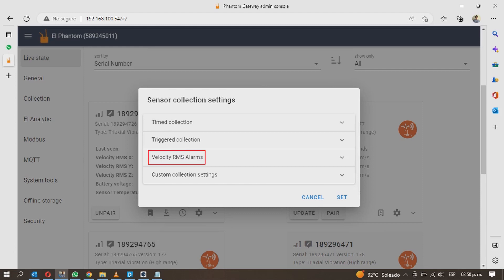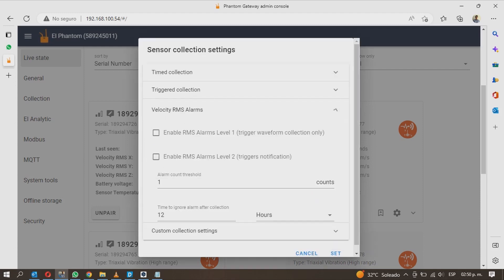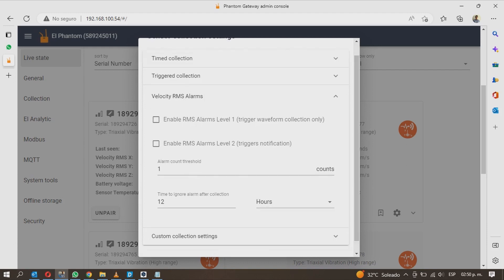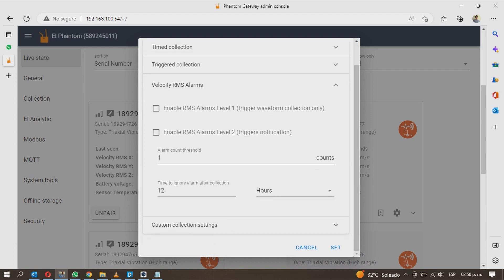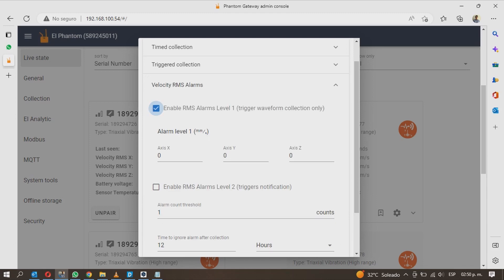The third section is called velocity RMS alarms. Here you can enable and disable the sensor alarms and you will have two levels of alarms. The level 1 alarm will cause the sensor to send the time waveform and FFT if the alarm threshold is exceeded on any of the measurement axis. Enter the alarm value for each axis.